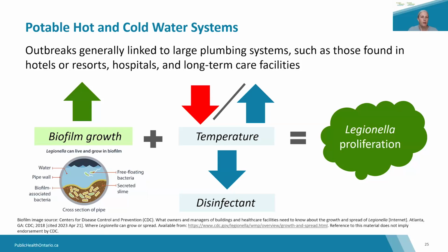Stagnation can also be affected by water use or intermittent water use and the type of the setting. So if you consider the water distribution in a private home compared to a facility that's at 75% occupancy or capacity, there may be rooms or wings that are not in use or have been repurposed that can lead to water stagnation in the plumbing system. So all these characteristics encourage biofilm growth, reduce temperatures and levels of disinfection, which can all lead to biofilm growth and Legionella proliferation. Next slide, please.